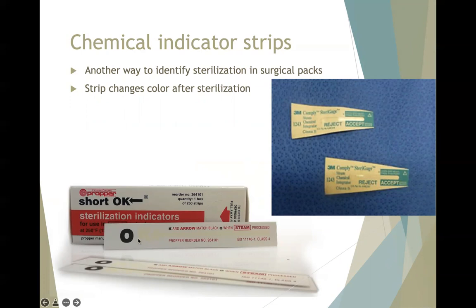So with these OK strips, we call them OK. They will say a big OK with an arrow pointing towards the K. As you can see, this is what they look like here before we've autoclaved them. So before we've put them through the steam autoclave, they're going to have that arrow and the K, they'll be white or kind of like a yellow in color. Once we autoclave it, it's going to turn to a dark color, and that's how we're going to know that we've successfully autoclaved our instruments.